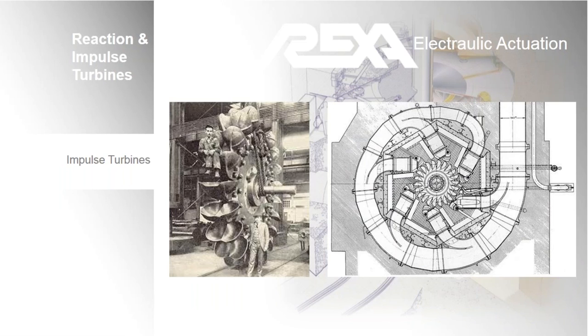Impulse turbines are different from reaction turbines as typically they operate at much higher head ranges, between 200 to 2,000 meters. Instead of having the runners submerged, the turbine is open to atmosphere. Pressurized water flowing through the system is converted into a high-velocity jet and released from the turbine nozzles that impinge on the runners of the turbine. Some turbines may have single or multiple nozzles depending on plant strategy.